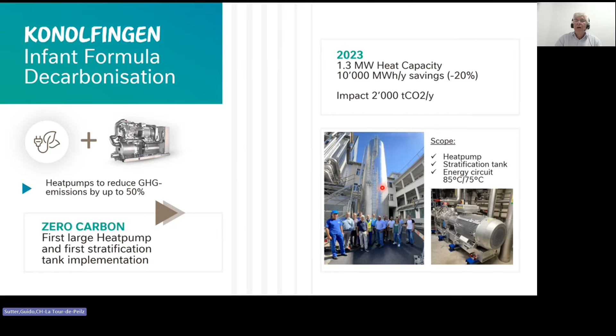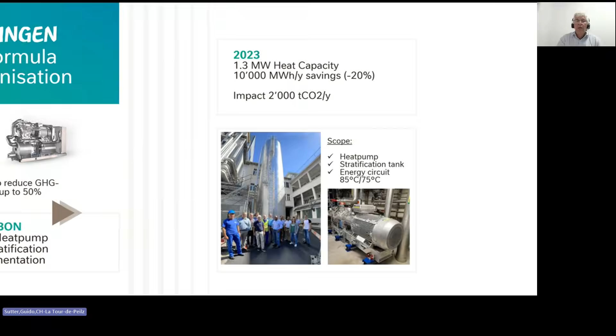So when we go to concrete examples, this is a project which was started up in 2023, Konolfingen, Switzerland, 1.3 megawatt heat capacity, 10,000 megawatt hour of savings. So you see, this plant is operating nearly 8,760 hours at full capacity to use the full heat from the heat pump, which is here. Heat pumps are not very sexy, it's just an engine, a compressor, and a motor. But what we have usually introduced always in combination with a heat pump is a stratification tank to make sure that differences in heat consumption and heat generation are stored in a half hour or 1 hour stratification tank in the form of hot water.